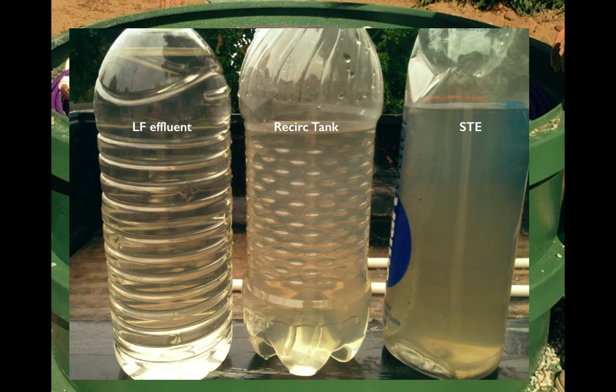Imagine on the right we've got septic tank effluent that's being mixed with the effluent on the left, the low flow effluent. Again, imagine one part of septic tank effluent and four parts of the clear low flow effluent, and what you would have is what's in the middle in the recirc tank. So it's this weak, dilute effluent that's actually being dosed to the low flow filter.